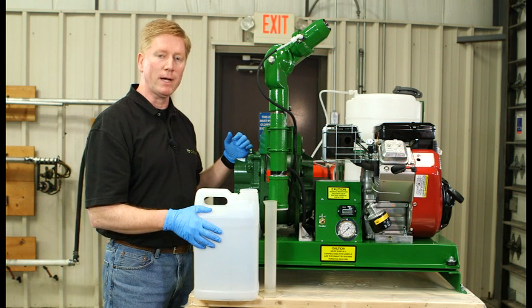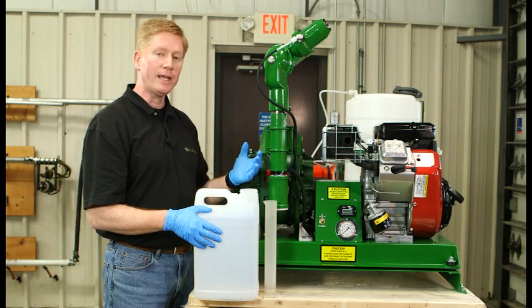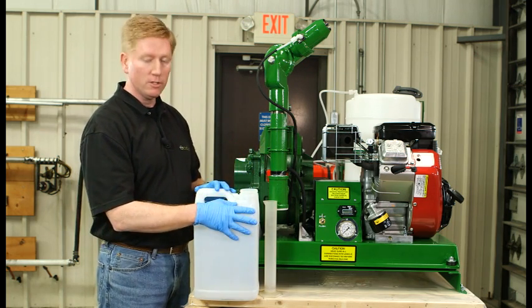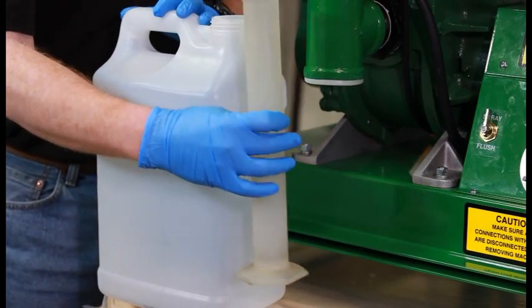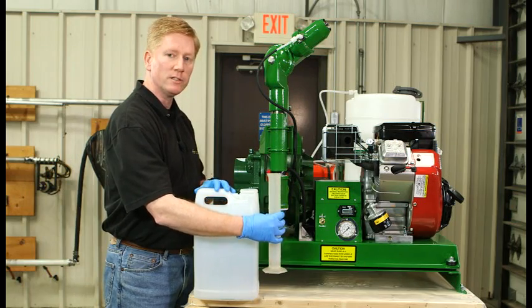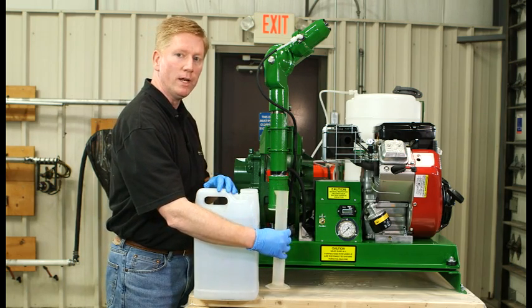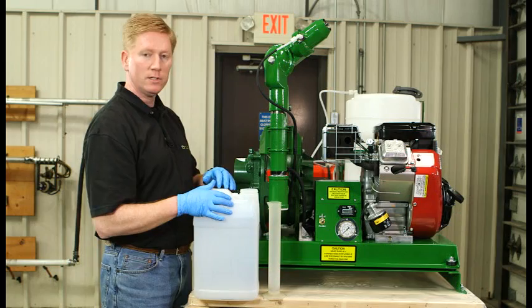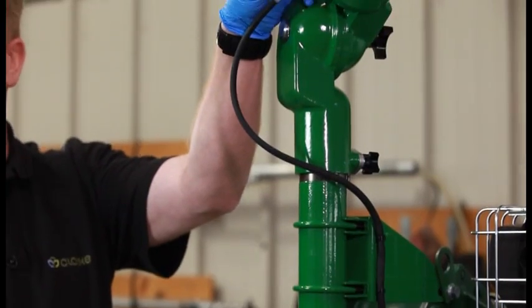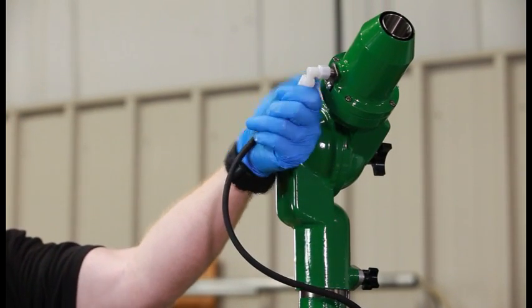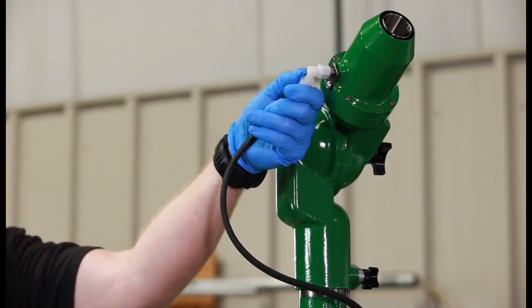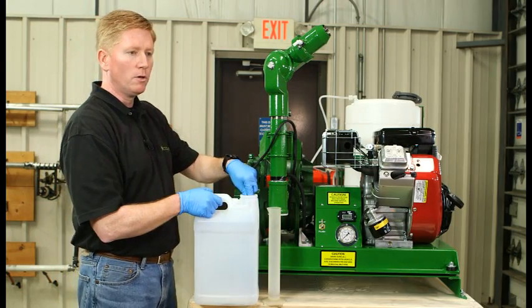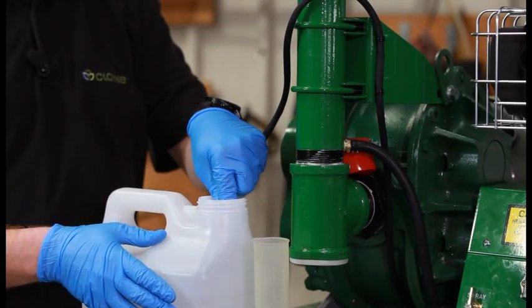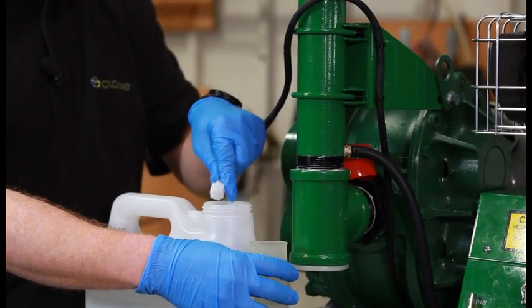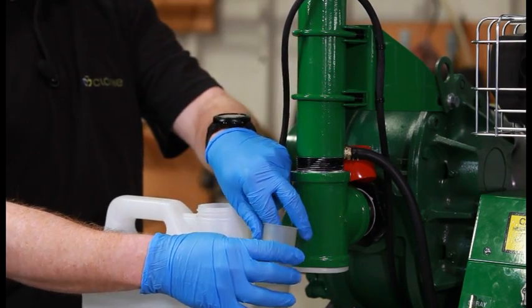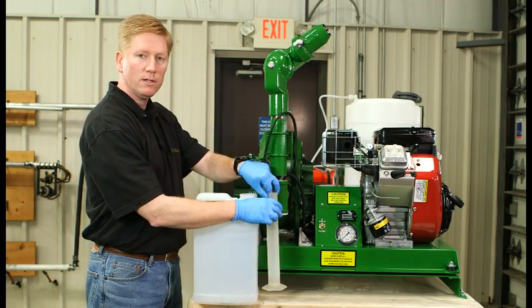After you've set your pump in your pump box, you need to come to the front of the machine and calibrate it to make sure that it's accurate. You need a receptacle to catch your chemical, and here we're going to use a 250 milliliter graduated cylinder that we're going to time for 1 minute to make sure that our pump is running accurate. To capture the chemical, we're going to come up here to the nozzle and disconnect our chemical line. Once our chemical line is disconnected, we're going to capture the chemical into our tank. Once all of our air bubbles are out, we'll come over here to our graduated cylinder, time our chemical for 1 minute to see if it's accurate.